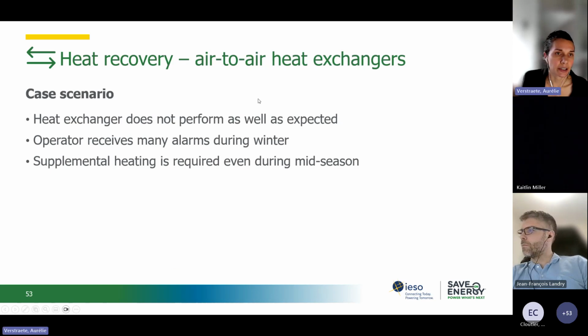For the first scenario, I want to talk about an air-to-air heat exchanger. You can have buildings where the heat exchanger does not perform as well as expected during the design phase. Maybe the operator receives many alarms during winter, and you see that you need supplemental heating even during mid-season.